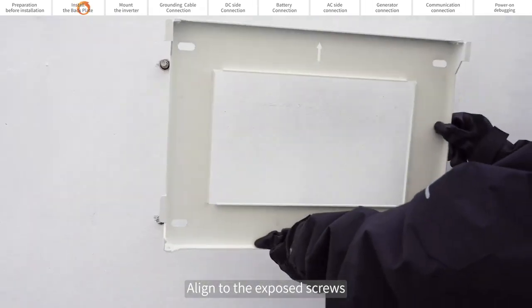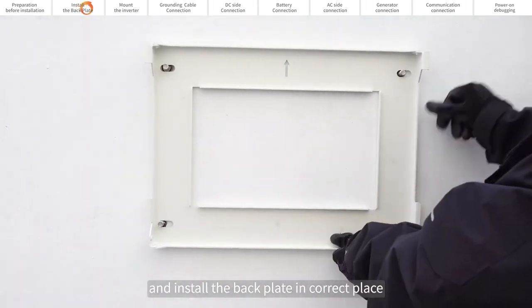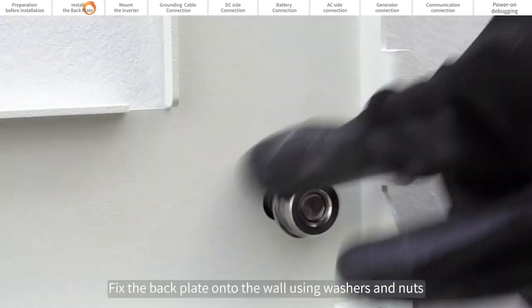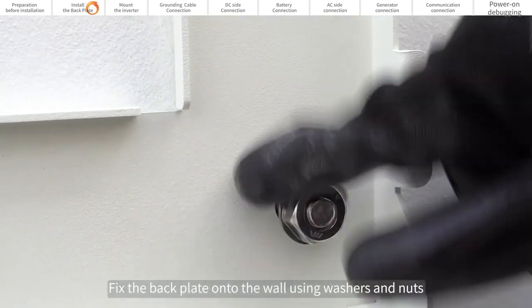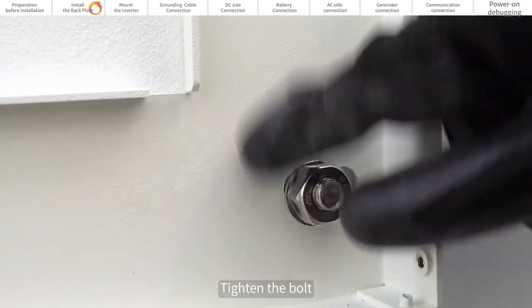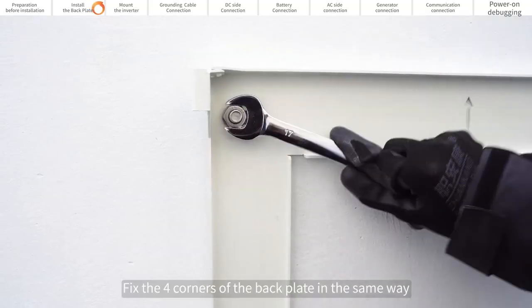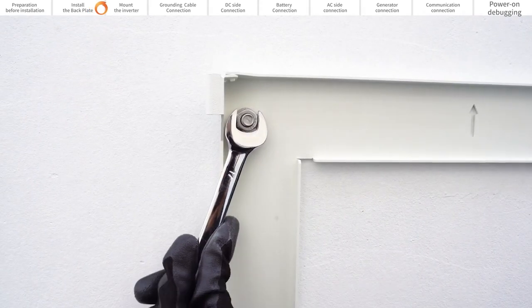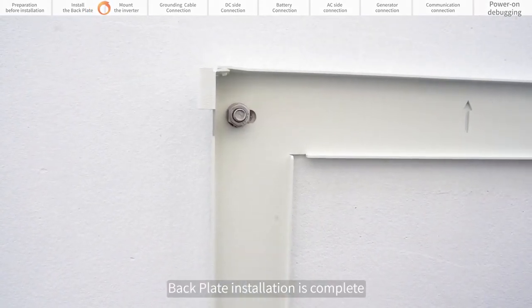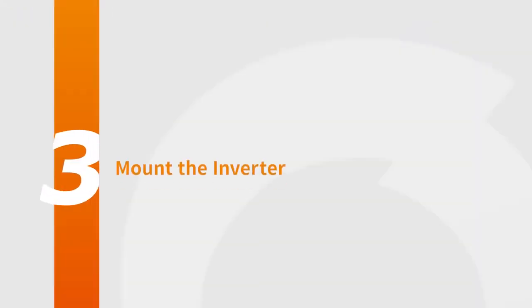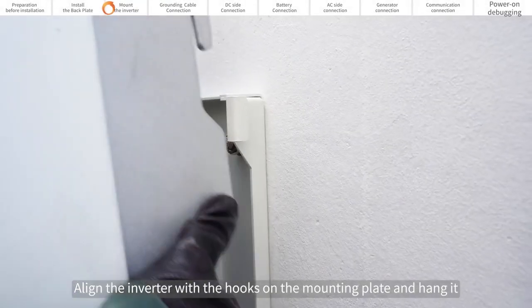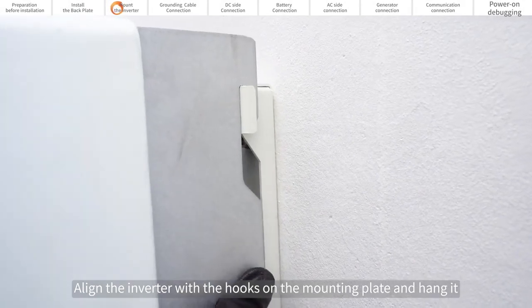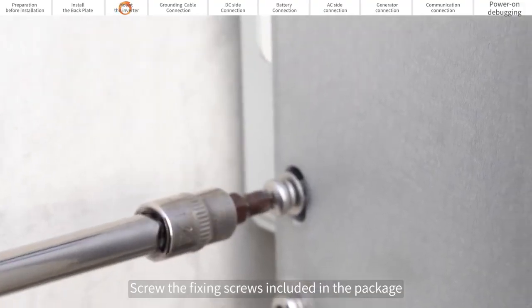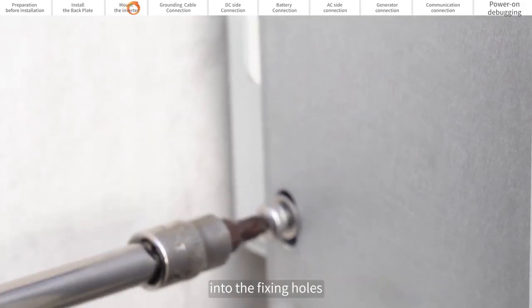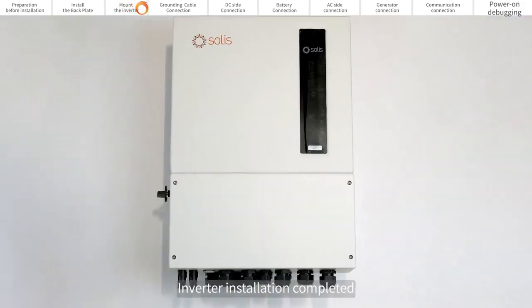Align to the exposed screws and install the back plate in the correct place. Fix the back plate onto the wall using washers and nuts. Tighten the bolts. Fix the 4 corners of the back plate in the same way. Back plate installation is complete. Mount the inverter. Align the inverter with the hooks on the mounting plate and hang it. Screw the fixing screws included in the package into the fixing holes. Inverter installation completed.